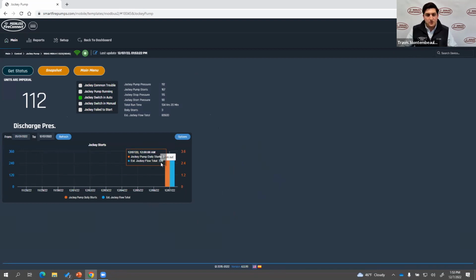So the orange here is your daily starts, and the blue is the amount of GPM basically in a 24-hour period. So based on the rating of that jockey pump and how long it's run that day, it will give you a rough estimate of how much water is actually flowing through there. So if you're trying to put numbers to an issue, this is a good way to do it.